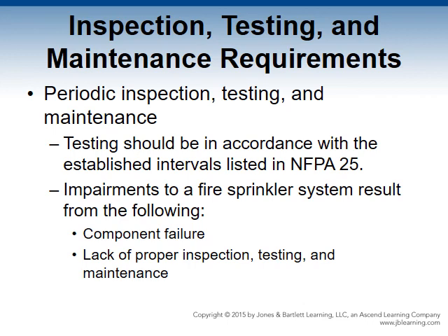A trip test determines if the dry, deluge, or pre-action valve will release and deliver water to the system in the appropriate time. A hydrostatic test on an underground FDC can determine if the piping remains intact or will fail when subjected to the apparatus pump pressure. Where cold weather conditions dictate, daily inspections of dry pipe, preaction, and deluge system enclosures are necessary. Whether it be weekly, monthly, quarterly, or semi-annual, inspections should be performed. Annually, all systems should receive a complete visual inspection and an operational test.